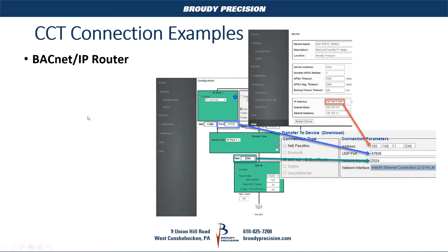If you use a BACnet router, you need to get into your BACnet router to find the settings — your network number, your BACnet port, and so on. In this example, I have a generic router where the router address is 192.168.1.249. The BACnet port is 47808, which is the default. The network number for the MSTP network is 2024. So in CCT, you'd enter 192.168.1.249 as the address, 47808 as the UDP port, and 2024 as the network number.